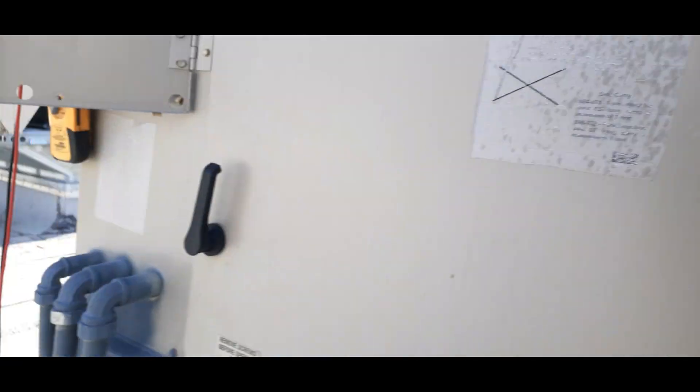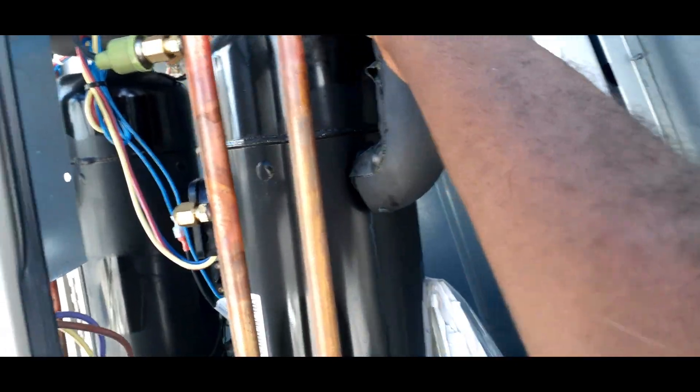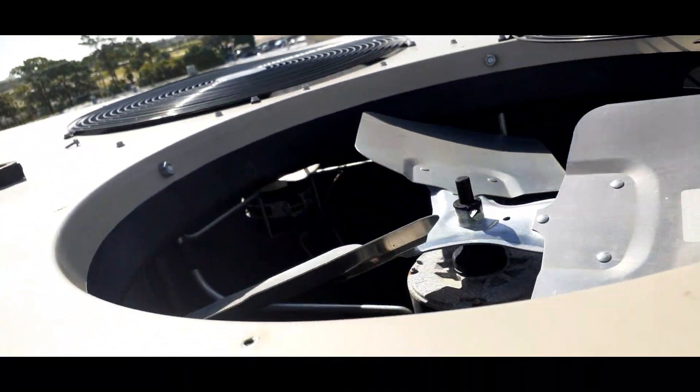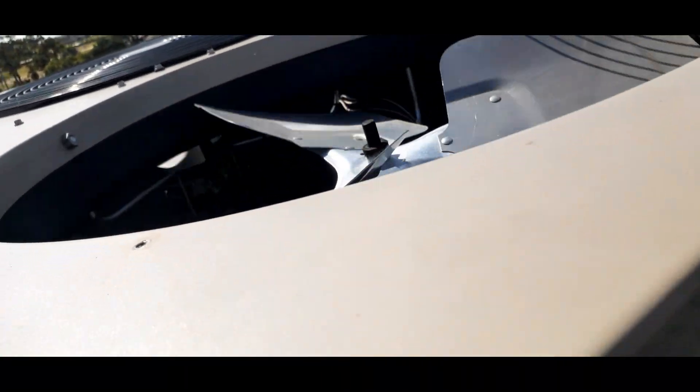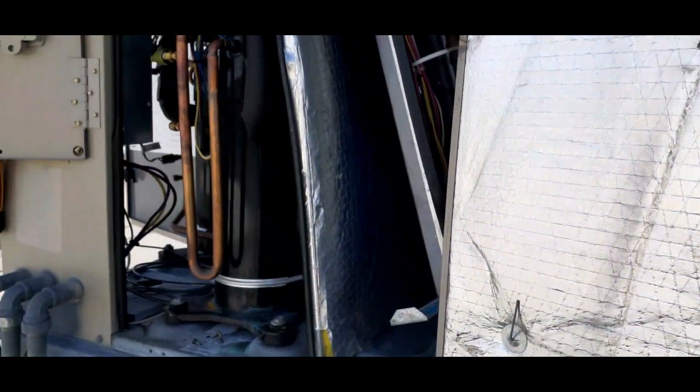Let's check our condenser fans. The compressor's running. Let's grab my ladder. Check our fans. All right, so that other fan is running. I'm probably gonna put some up here like a cardboard, something to come back, so new motor and a new adjustable pulley.